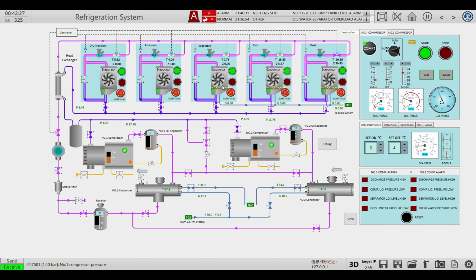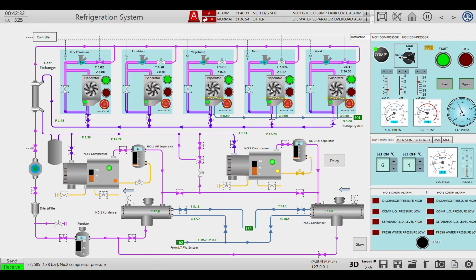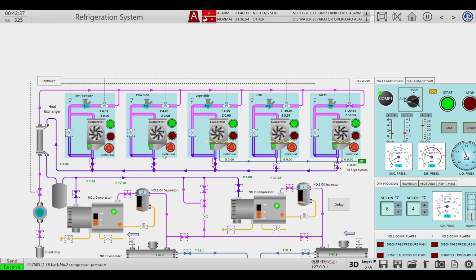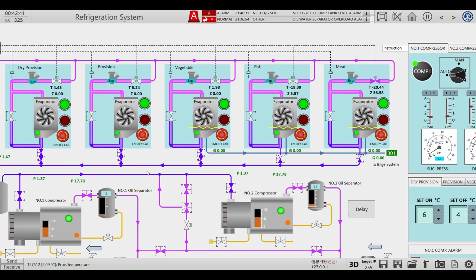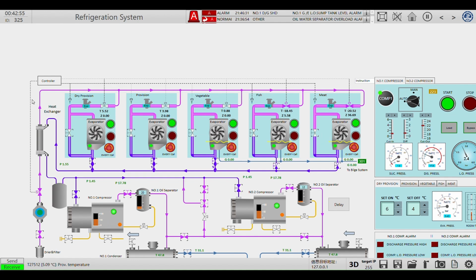And you can see for this, here it is. This is the dry provision and provision in the vegetable room. You will see this special kind of valve. So what is this valve? It is throttling the flow such that the pressure is maintained. If you reduce the boiling point pressure, the boiling point reduces. But we have to maintain the temperature at 5 degrees Celsius. So we have to make sure that the pressure does not fall below that. According to the pressure, there is a corresponding boiling point, or you can say saturation temperature. So you have to keep the pressure in the evaporator coil in such a way that the saturation temperature of the refrigerant does not fall below 0 degrees Celsius.